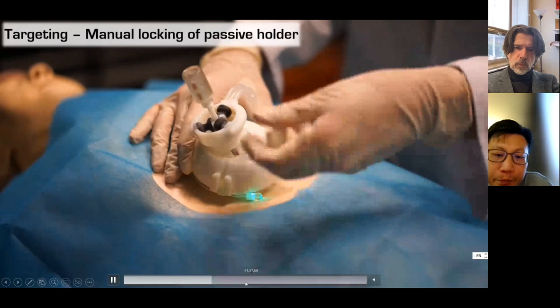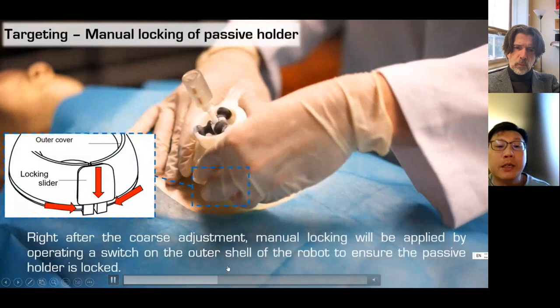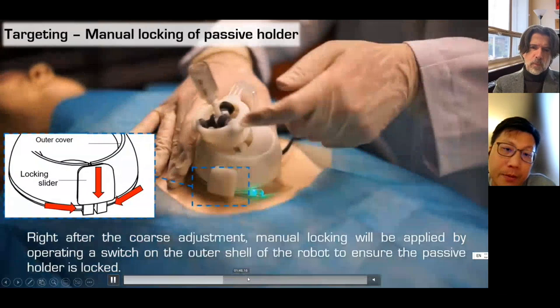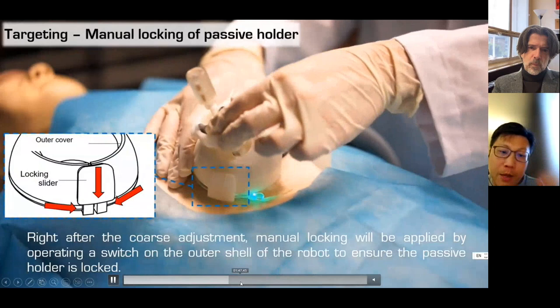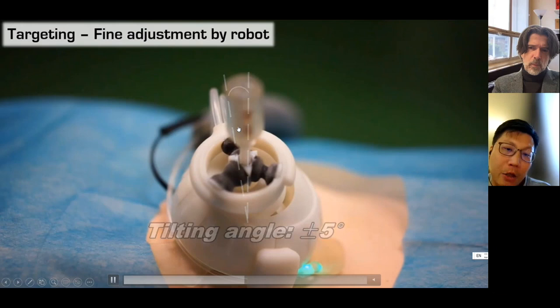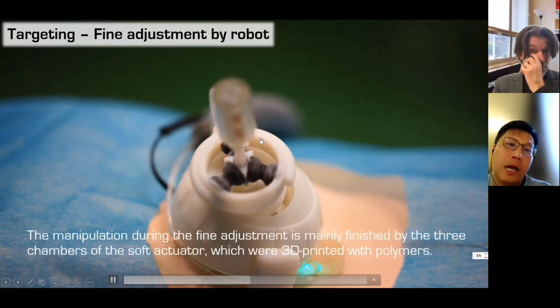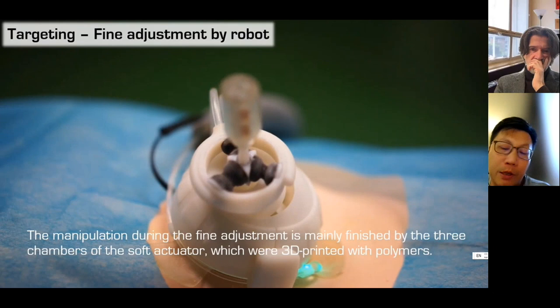So the surgeon has to fix and lock it, but that may not be accurate. When the patient goes back into the MRI, we use the soft actuator to fine tune the needle guide to the right place, compensating within a 5 degree error.